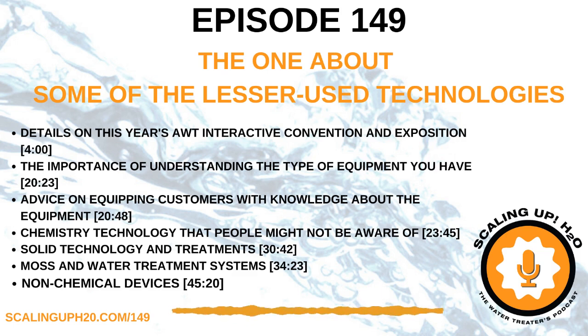We've got enough minerals in there that, as long as we don't have unique situations such as low hardness levels, we have corrosion rates of 1 to 1.5 on mild steel, and copper are 0.05 up to about 0.2. The results show us very good control of your corrosion rates in the system.